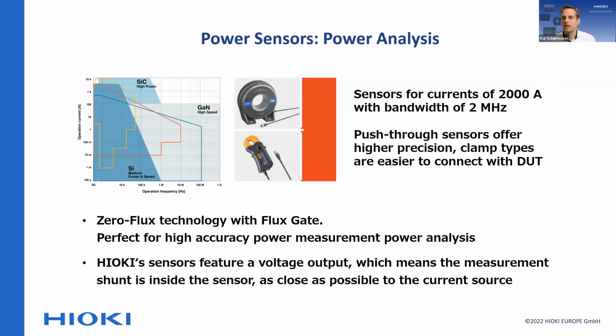That's why in power analysis, the sensors typically used are zero flux technologies with a flux gate. They bring the possibility to do high accuracy power measurement or power analysis. The important part is the bandwidth isn't as high, but that's down to the fact that they don't use the Hall effect principle, but a flux gate system instead. The positive thing is they don't drift, and that's really something you want to ensure in power analysis.